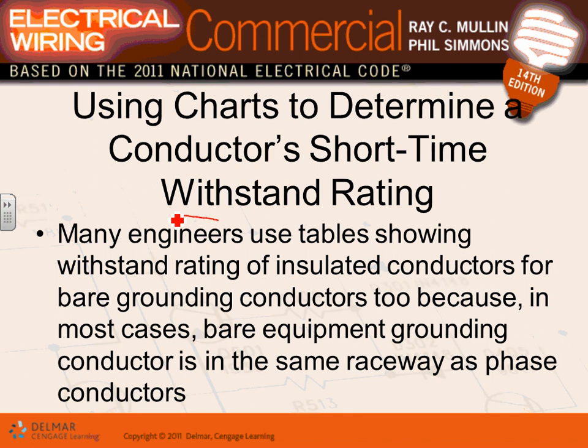For withstand rating, many engineers and engineering designs use tables, except what we are using for all this is SKM PTW, the damage curve. The nice thing, when I go through the software in a few seconds, is that you don't have to worry about this calculation. In the software, you grab a conductor, 500 kcm, and here's the damage curve for it. If your conductor is number 10, here's the damage curve for it. If your conductor is 1000 or 1200, here's the bigger curve for it. All of this has been tabulated by smarter people a long time ago and put in the software for you and I to use through SKM and any other software.